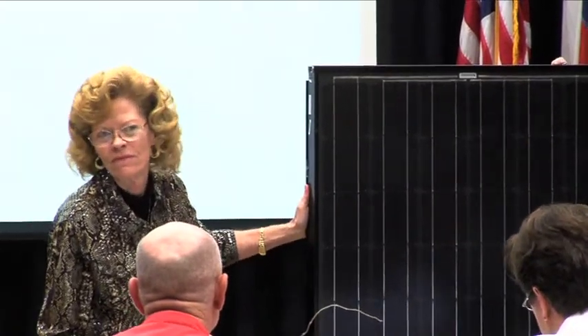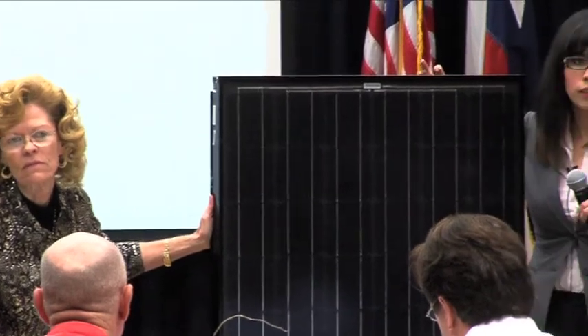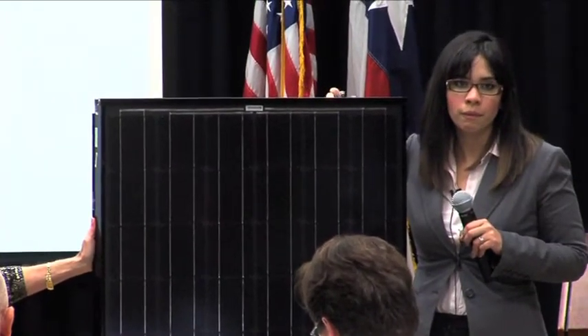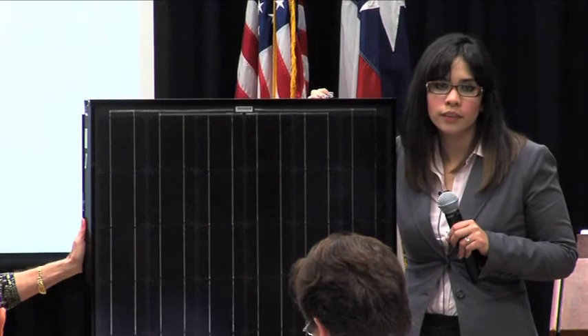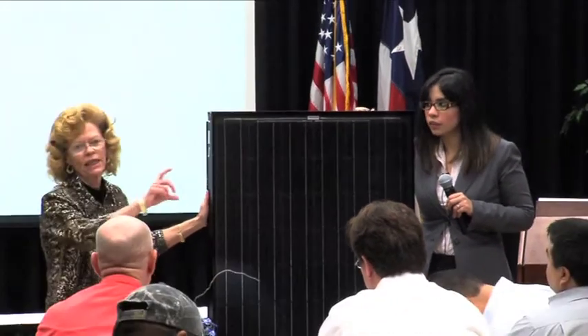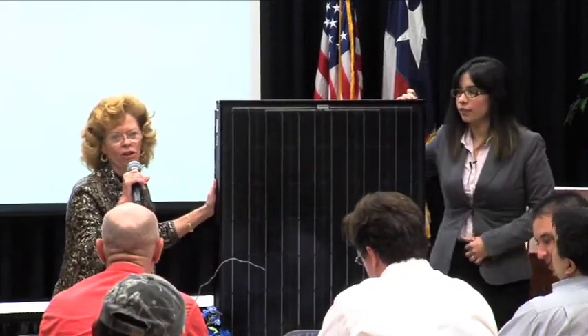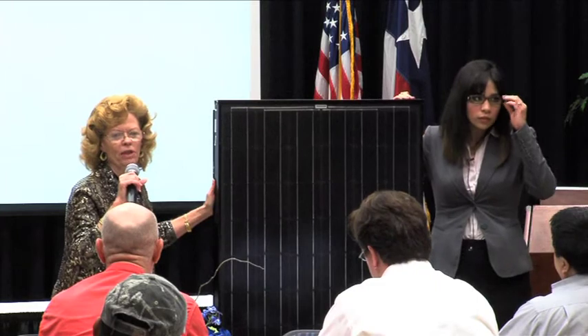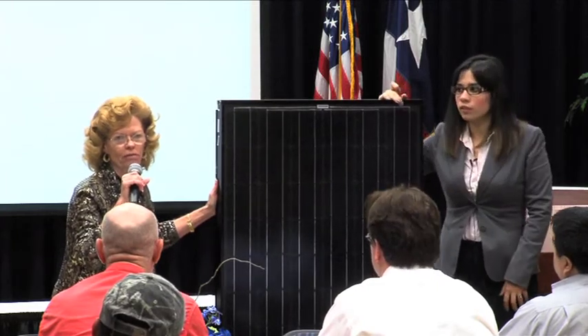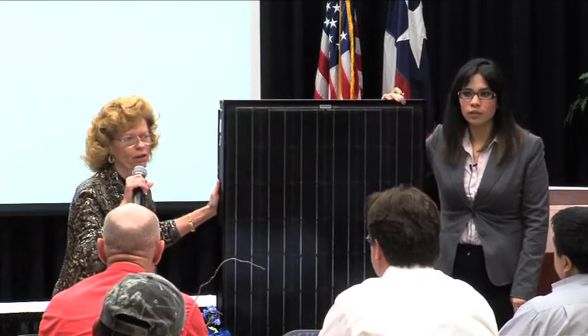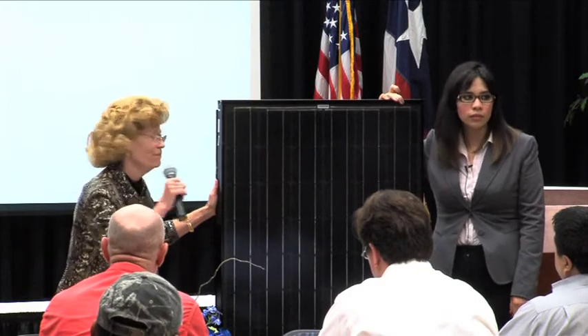Now, you have the option of not putting it on the rooftop. You can put it on a separate panel, if you will, and not have to worry about retrofitting. You can string from the rooftop unit to the nearest panel. We recommend that you not go over 200 feet. But that's a pretty good area for you to go.